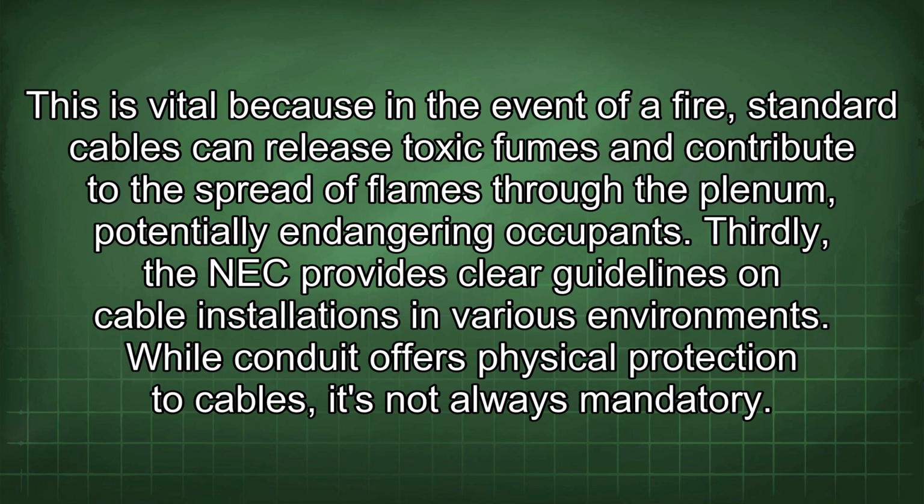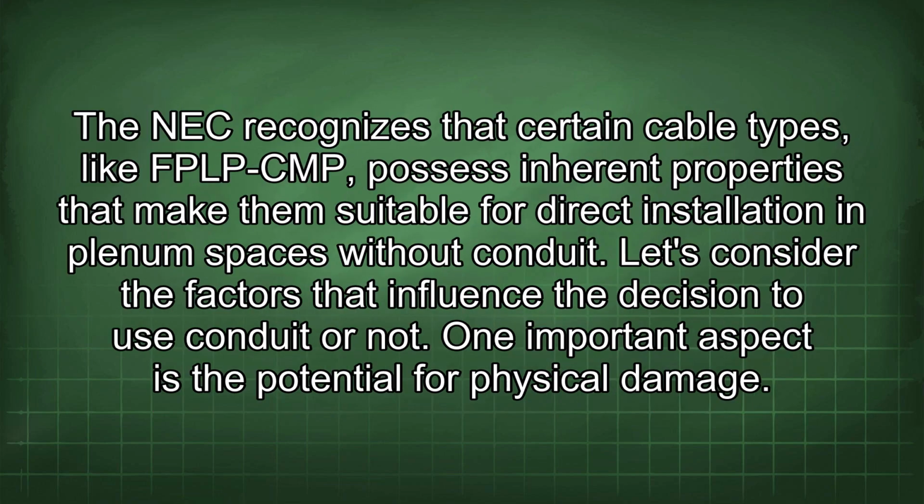Thirdly, the NEC provides clear guidelines on cable installations in various environments. While conduit offers physical protection to cables, it's not always mandatory. The NEC recognizes that certain cable types, like FPLP CMP, possess inherent properties that make them suitable for direct installation in plenum spaces without conduit.